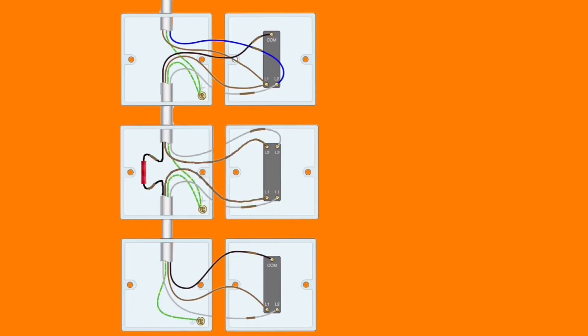The two-way switch now appears at the bottom, fed from a three-core from the switch above. In real terms, the two-way switch has moved down a position to the bottom. For two-way and intermediate switching: the first switch is a two-way switch, you can have as many intermediate switches as you like - I've shown only one here - followed by a final two-way switch. So you could have 20 intermediate switches as long as the first and last switches are two-way switches.